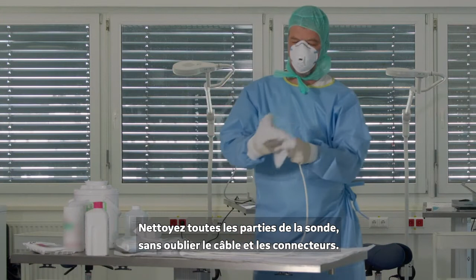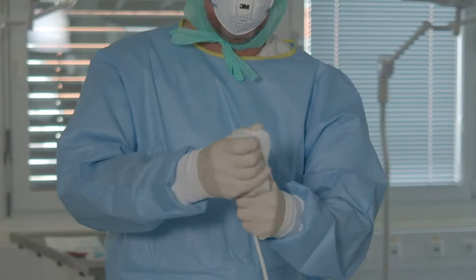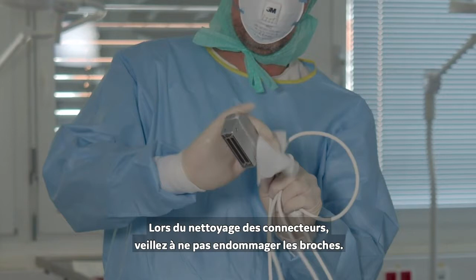Proceed to cleaning the transducer. Be sure to remove all visible debris and to clean all parts of the transducer, including the cable and connector. Finally, disinfect the transducer again and finish off by wiping its cable as well. Replace with new wipe if dry. When cleaning the connector, be careful not to damage the pins.